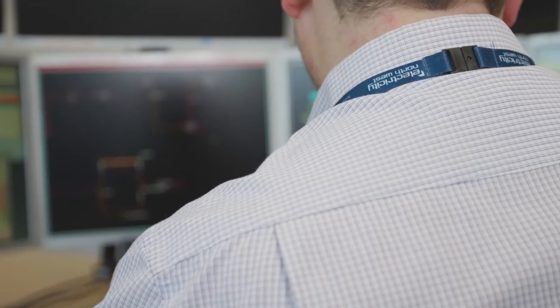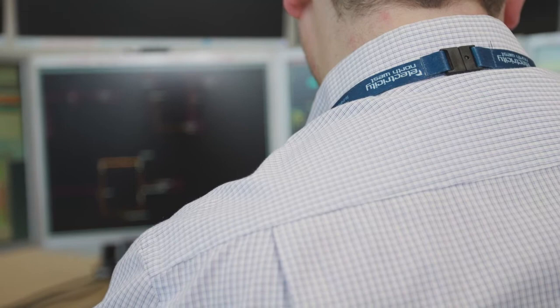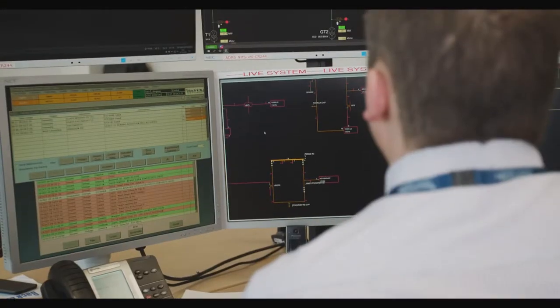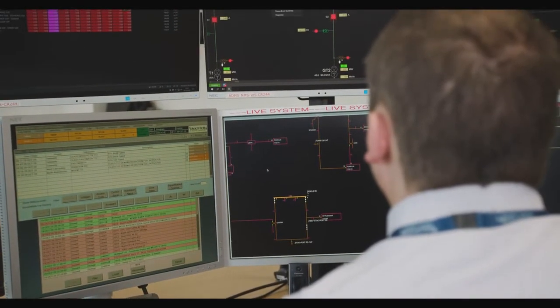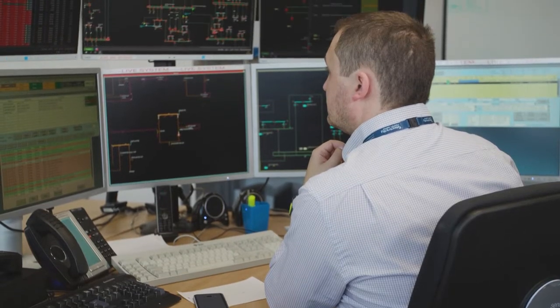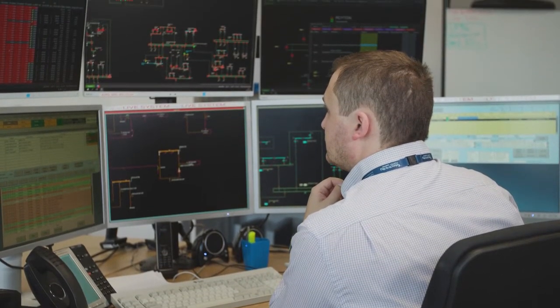Then in terms of the dangerous situation I was talking about before, the low line, at the moment the only way we can identify those is by the public calling in and saying that they've seen something. In those instances, we would dispatch an engineer immediately, and we would also identify off the HV network, as well as using geographical tools, that HV circuit, and we will actually make that dead to ensure safety of the public.